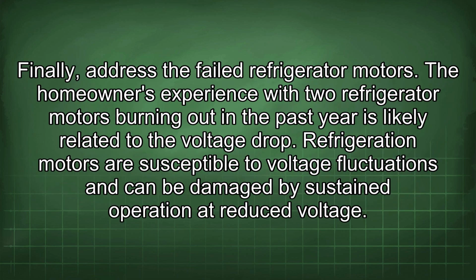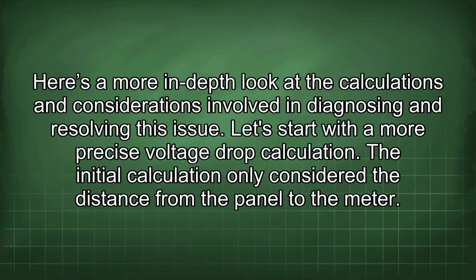Finally, address the failed refrigerator motors. The homeowner's experience with 2 refrigerator motors burning out in the past year is likely related to the voltage drop. Refrigeration motors are susceptible to voltage fluctuations and can be damaged by sustained operation at reduced voltage. Here's a more in-depth look at the calculations and considerations involved in diagnosing and resolving this issue.